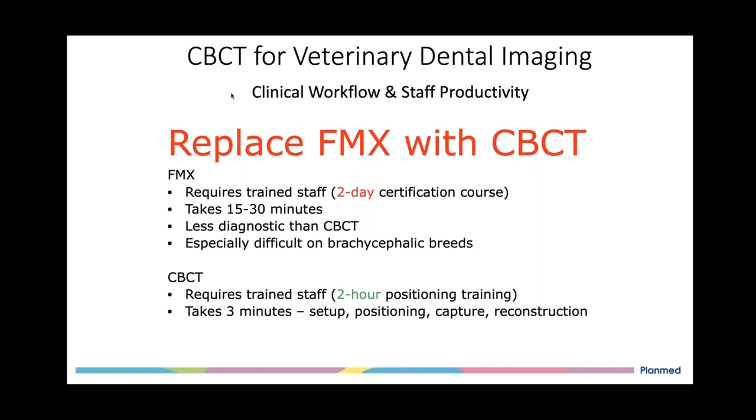The actual image where you're pushing the button, exposing the patient, is 15 or 20 seconds at the most. But that 3 minutes is the entire setup, getting the computer ready, positioning the patient properly, the capture of the image, and then the reconstruction of that image afterwards. Remember, taking the individual 400 or 500 images and reconstructing them into our 3D representation.